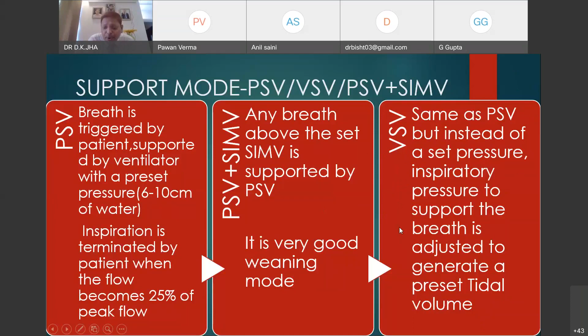So this is the volume support mode. It is the same as the pressure support mode, but instead of a set inspiratory pressure for the support, the breath is adjusted to generate a preset tidal volume. So here pressure is adjusted to deliver a set tidal volume. This is the volume support mode of ventilation.